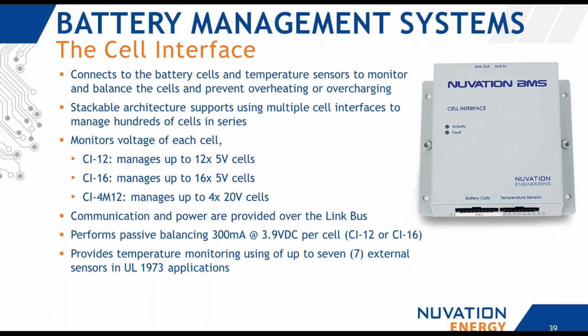We also offer a version that manages monoblocks. So this is our CI 4M12 variant. It talks back through a proprietary link bus to our stack switchgear, and they can perform balancing up to 300 milliamps for CI12 and CI16, and you get 7 temperature sensors.